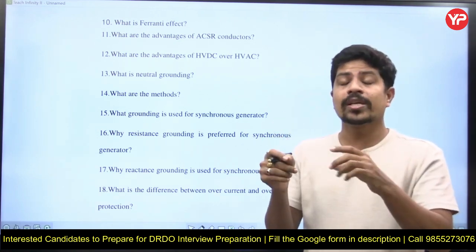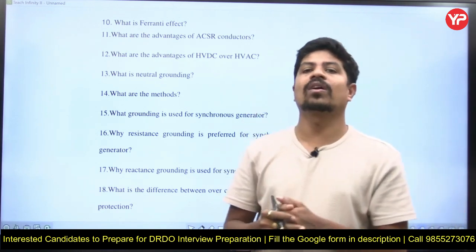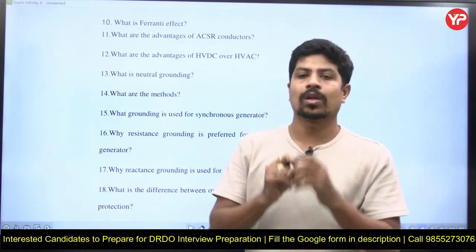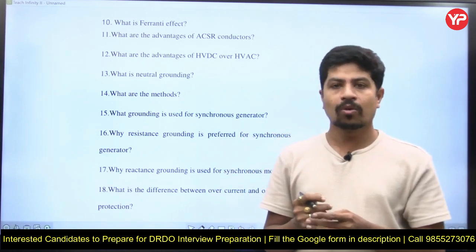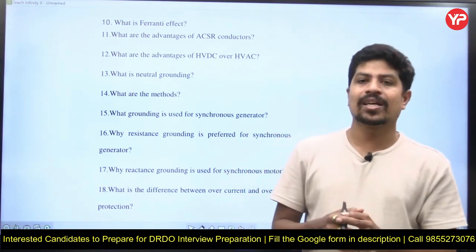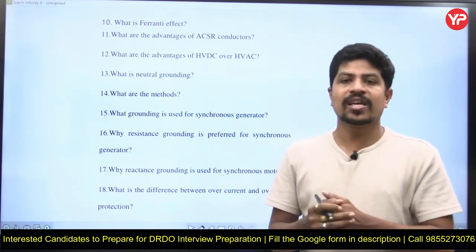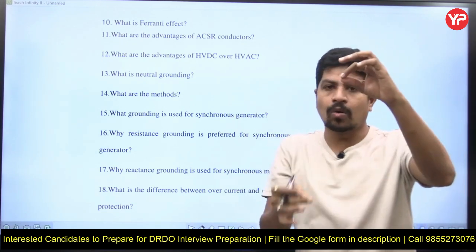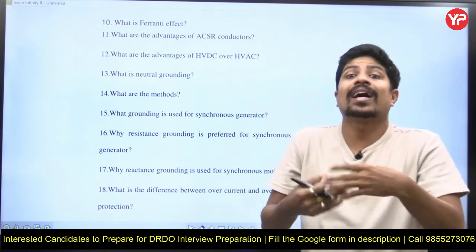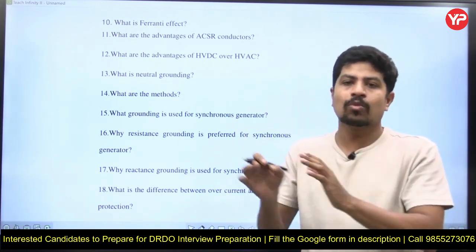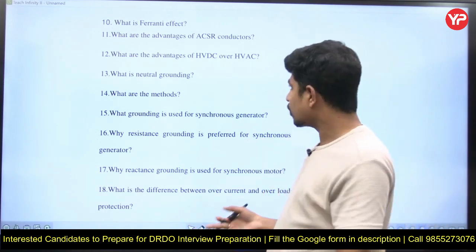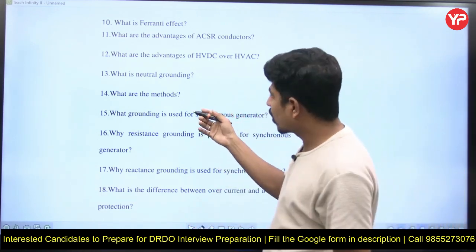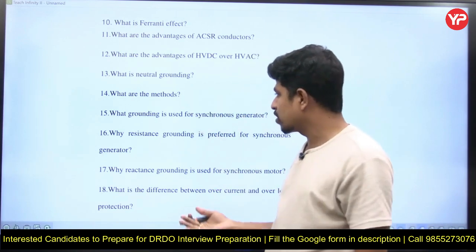The purpose of neutral grounding is to provide a closed path for the flow of fault current and to avoid a floating neutral. Earthing is different: connecting the body of equipment to the ground for operator safety is called earthing. Neutral grounding and earthing are not the same. Another question is: what are the different methods of neutral grounding?